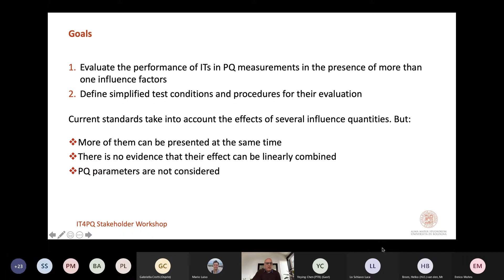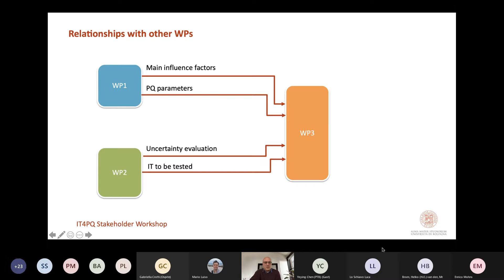To reach these results, Work Package number 3, of course, as I said before, needs several inputs from the previous work packages. In particular, it is expected that Work Package number 1 will provide to Work Package number 3 information about the main influence factors to be taken into account and the power quality parameters to be evaluated in presence of these influence factors. And from the Work Package 2 side, it is expected information on uncertainty evaluation and the kind of instrument transformers to be tested, and finally information about the reference generation and measurement setup.